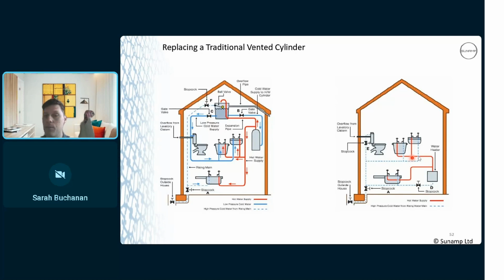You would just be looking at that pipework insulated there. So somebody mentioned a back expansion relief valve, or a 6-bar PRV as we all know it. If you can get away with a flow group combination valve, brilliant. You can just tie into the D2 and obviously drain away your expansion from there.